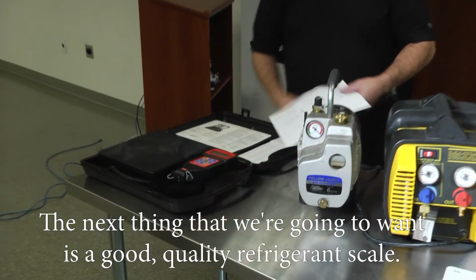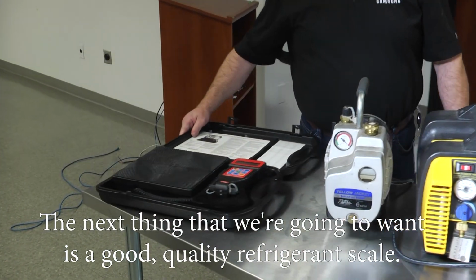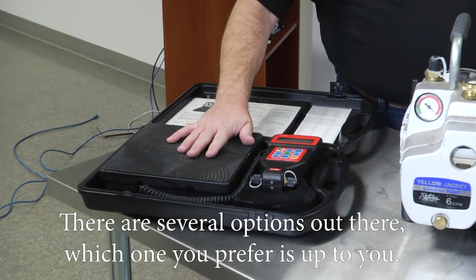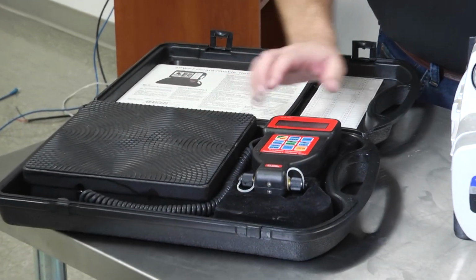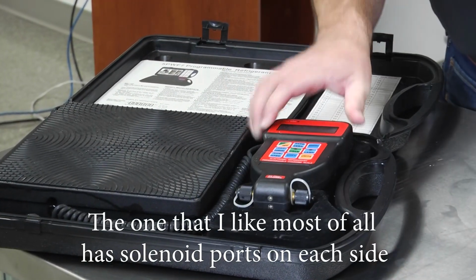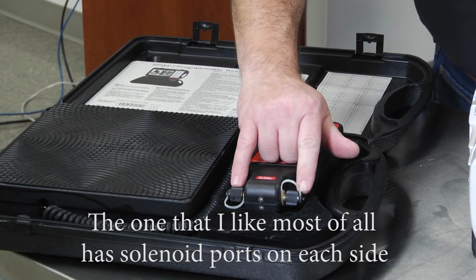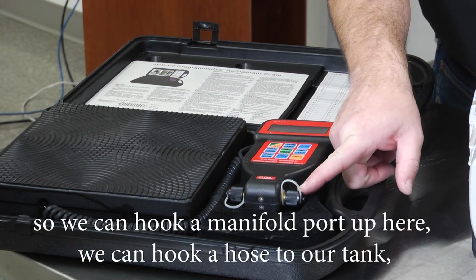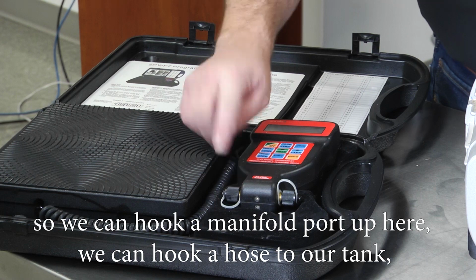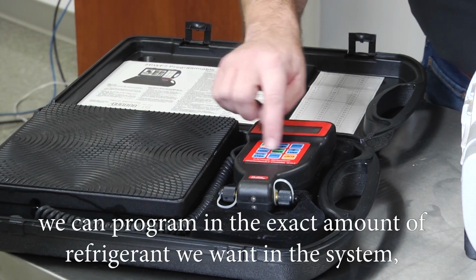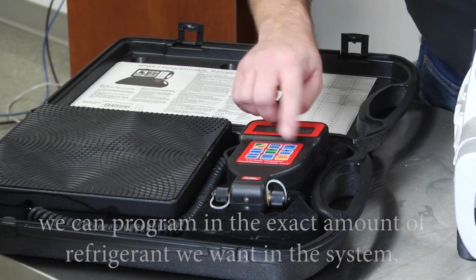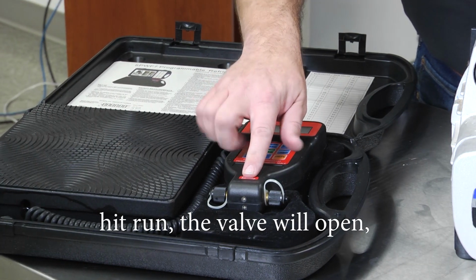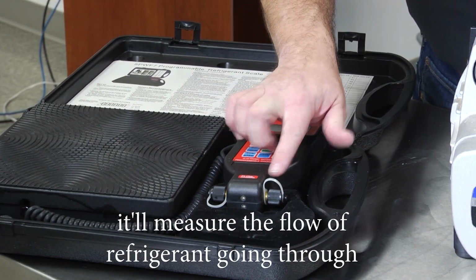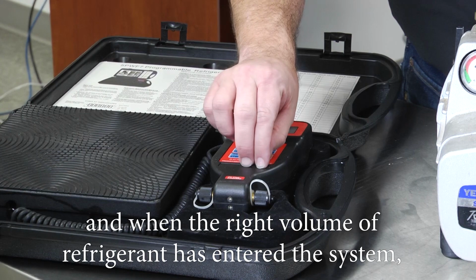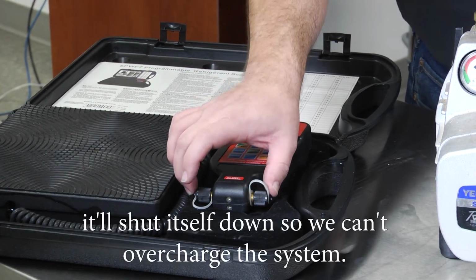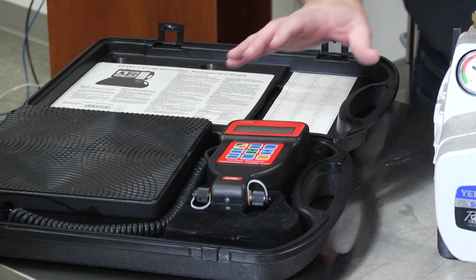The next thing that we're going to want is a good quality refrigerant scale. There's several options out there, which one you prefer is up to you. The one that I like most of all has solenoid ports on each side, so we can hook a manifold hose up here. We can hook a hose to our tank. We can program in the exact amount of refrigerant we want in the system. Hit run, the valve will open. It'll measure the flow of refrigerant going through, and when the right volume of refrigerant has entered the system, it'll shut itself down so we can't overcharge the system.